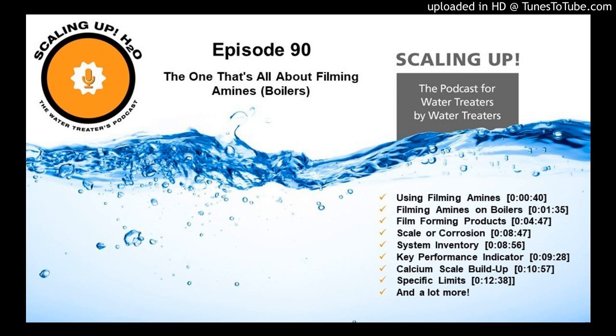So in the world of dosing without a meter, we can do the math, and then we would just monitor for filming amine residual in specific locations so that we could say, okay, well, in here, we seem to be dosing appropriately. We've got a healthy residual. We have no iron, right? There's no corrosion actively occurring, and we've got a decent pH. Okay, we're covered. We're good. There you go. I think there is a lot of confusion around that though.